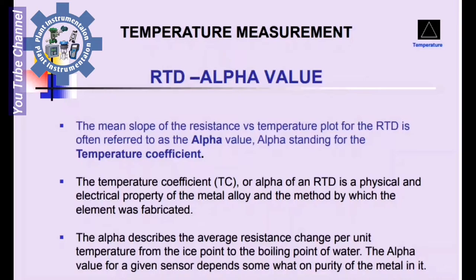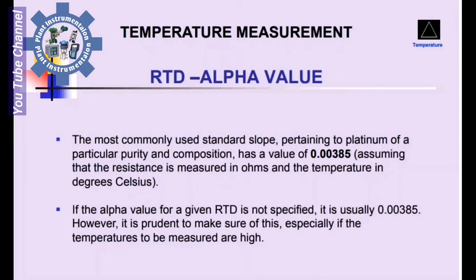The alpha describes the average resistance change per unit temperature from the ice point to the boiling point of water. The alpha value for a given sensor depends somewhat on the purity of the material. The most commonly used standard slope for Platinum has a value of 0.00385, assuming resistance is measured in ohms and temperature in degrees Celsius.